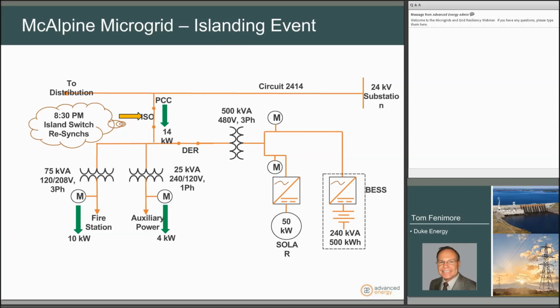The battery went back to an idle condition and was ready to operate again if it needed to support the fire station for microgrid operation. This was our first unattended islanding event, and everything operated as planned. We've since had several other events where the operation has been exactly the same way.